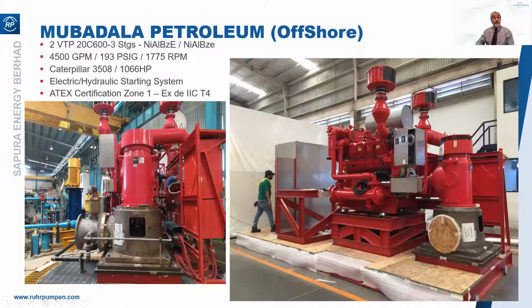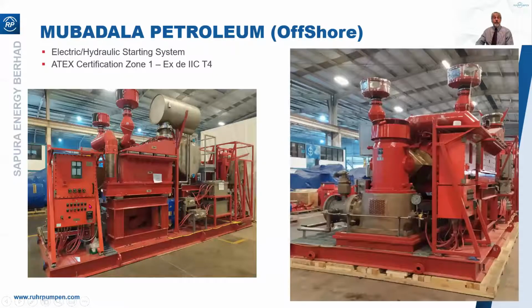Now here we have hazardous area sets. You'll see ATEX certified, Zone 1, Ex de, IIC and T4. So we will see on this, especially from the other side, here we go, explosion-proof electrics and control panel, flame traps on the air intakes, purged battery boxes, enclosed exhaust manifold and silencer.